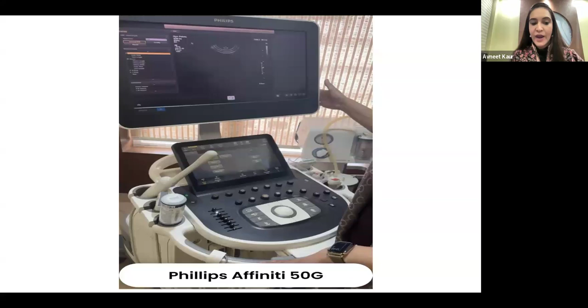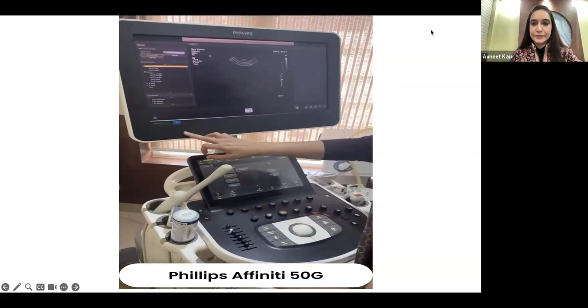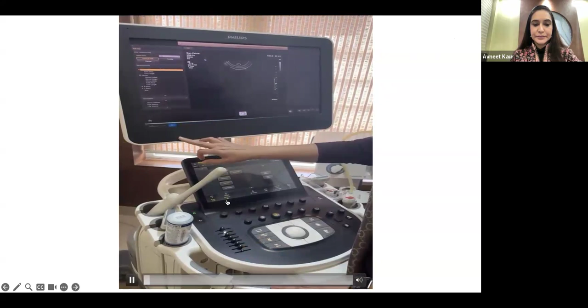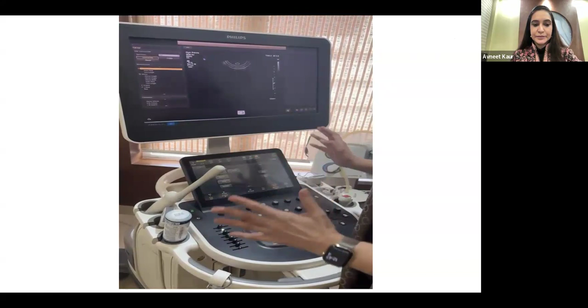So my first video which I'm playing is basically how to acquire the image. It tells you about the machine and how to acquire the image. I've tried to make some videos, divided by the Philips Affiniti 50G. It's very important whenever we are using any machine to know about the knobs, because without knowing the gears, we cannot drive a car. Similarly, without knowing the knobs, we cannot run our machine. So first we'll let you know about all the knobs, the screens and whatever is available, the transducers, what type of transducer, and how to connect the transducers while using this machine.